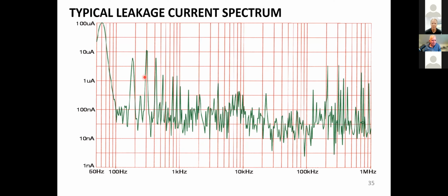And this particular signature, odd order harmonics, is due to the flat topping of the sine waves, which is largely caused by electronic power supplies that draw current only at the tips and the peaks of the AC power. So it tends to flatten the waveform on the grid that way, and it shows up as harmonics. So this would show up as somewhere around 2 or 3 or 4% harmonic distortion. But be very, very careful connecting to the power line. This was done with an isolation transformer.